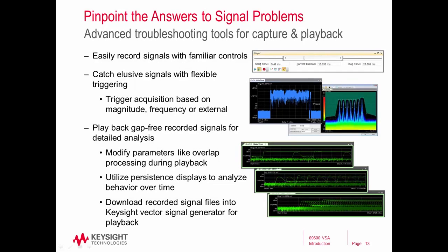In addition to acquiring signals for live measurements, the 89600 VSA software can also be used to record signals for playback later or to troubleshoot a signal. There's a player that can be used to easily record and then play back these signals, along with triggering to define when you would like to start the acquisition — very helpful for catching elusive signals. Playback of these signals is gap-free, and you can modify parameters like overlap processing to slow down or speed up playback. You can utilize persistence displays or spectrogram displays for more information, and source control enables you to play back a recorded file through a signal generator.